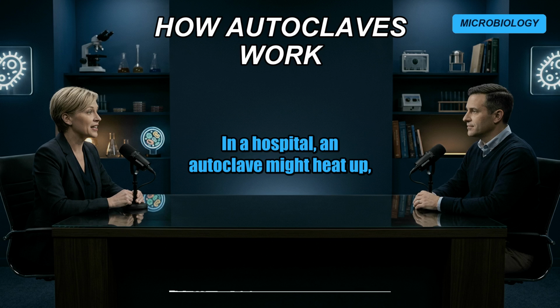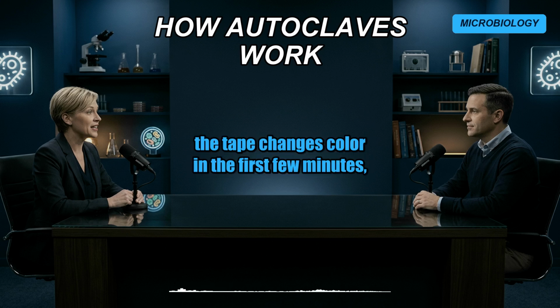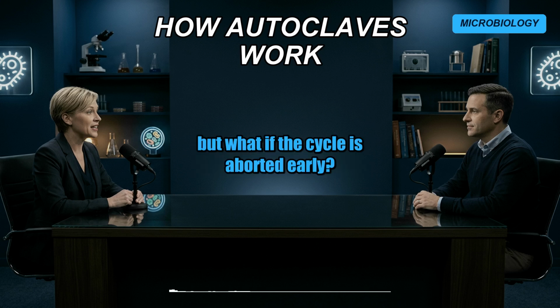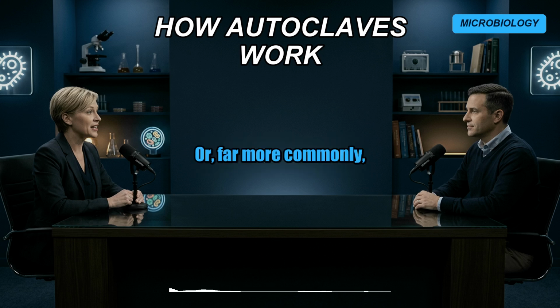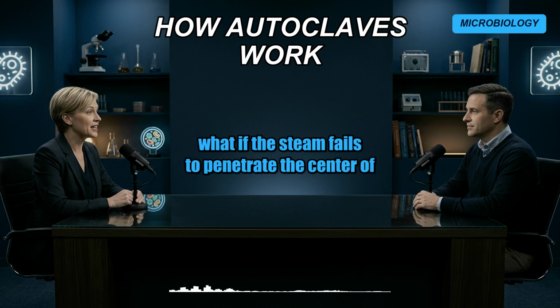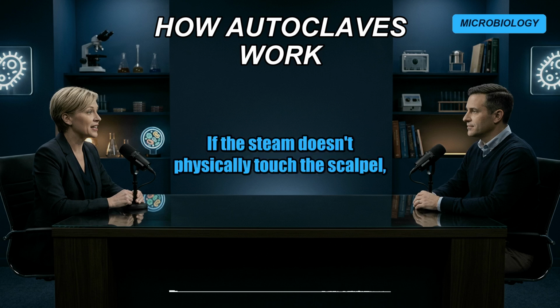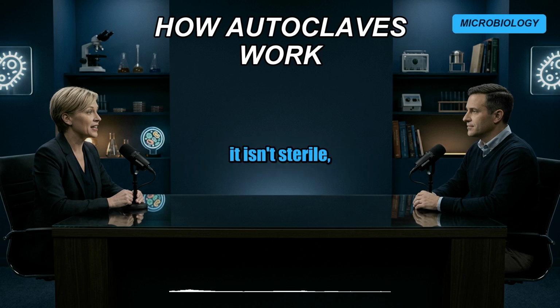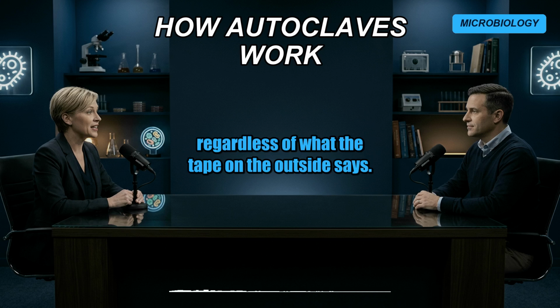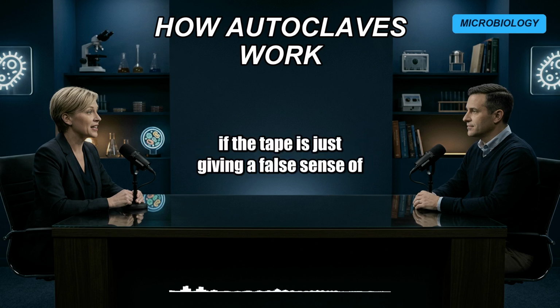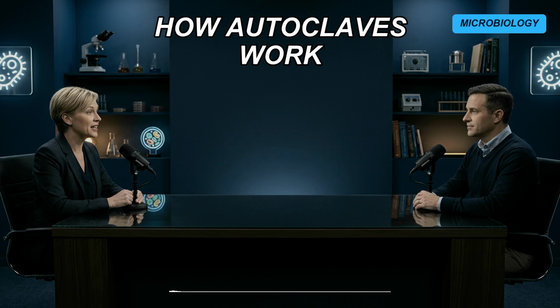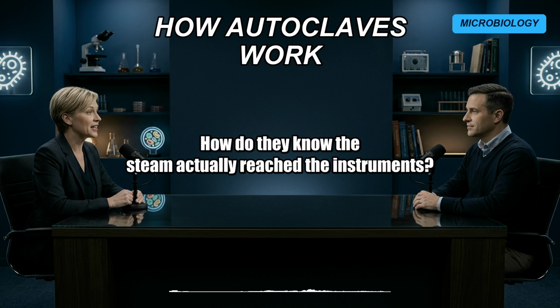In a hospital, an autoclave might heat up, the tape changes color in the first few minutes, but what if the cycle is aborted early? Or, far more commonly, what if the steam fails to penetrate the center of the surgical tray? If the steam doesn't physically touch the scalpel, it isn't sterile, regardless of what the tape on the outside says. So if the tape is just giving a false sense of security, what is the actual proof? How do they know the steam actually reached the instruments?